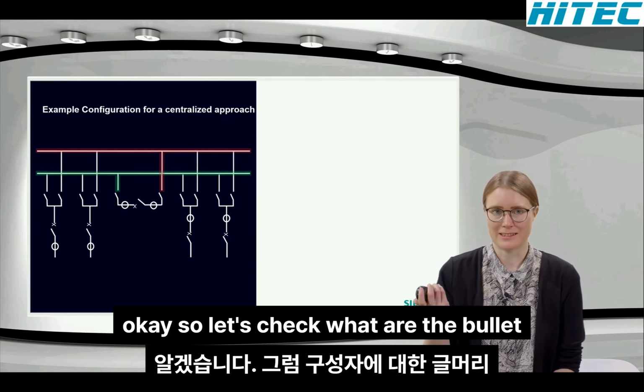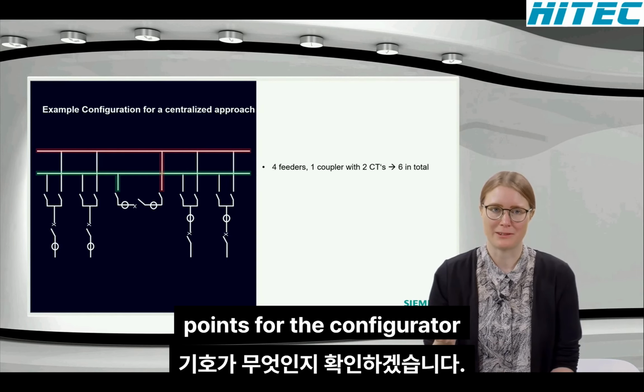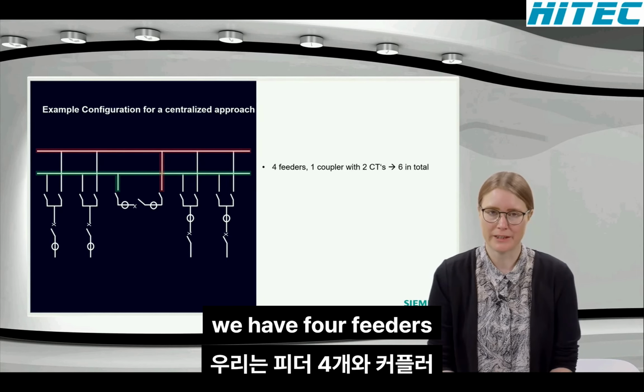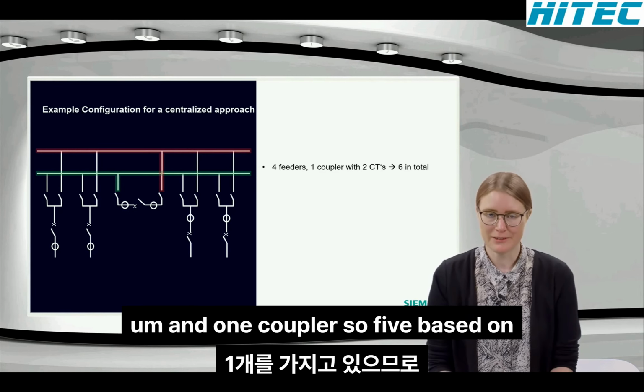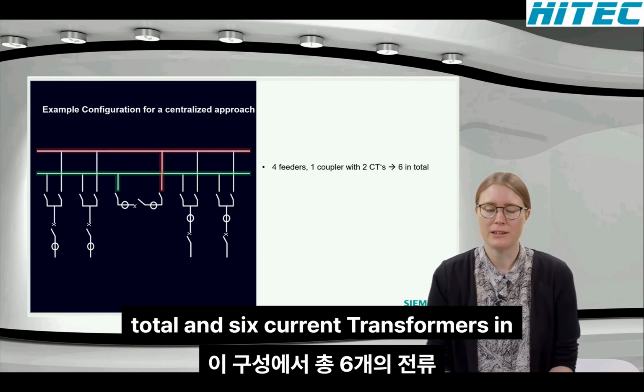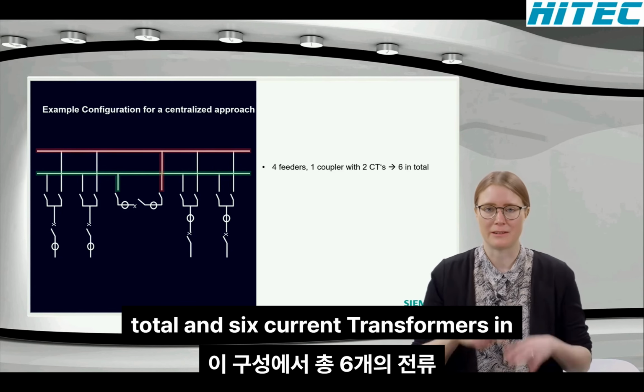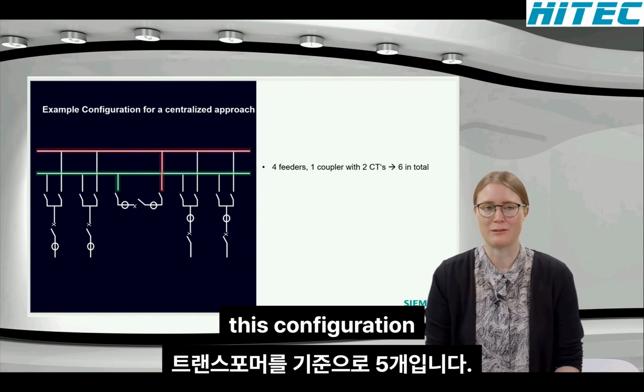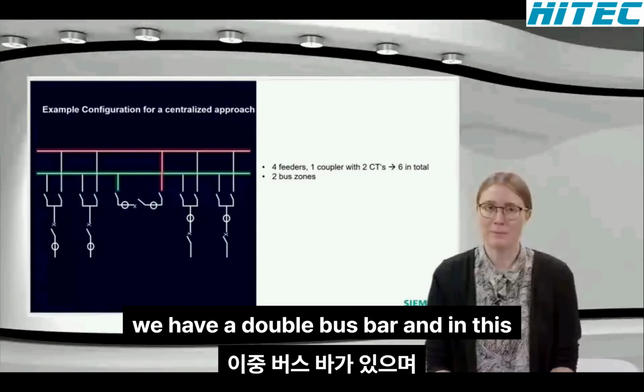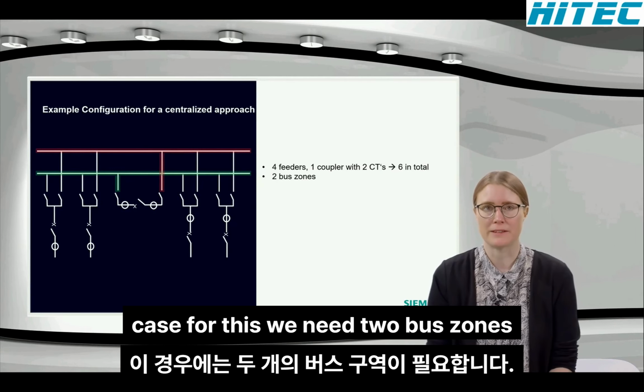Okay, so let's check what are the bullet points for the configurator. We have 4 feeders and 1 coupler, so 5 bays in total, and 6 current transformers in this overall configuration. We have a double busbar, and in this case, for this, we need 2 bus zones.